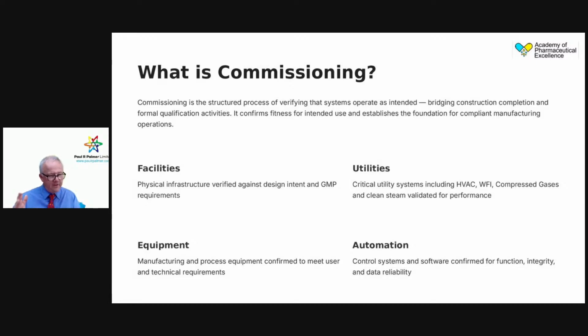Imagine that. You've had your inspection, everything's fine. We've looked at how you're going to do your commissioning, what your plan is, based on your SOPs. But then you go to the site and they won't let you take any pictures, and they won't let you take your digital notebook into the facility because they've got a higher specification than you're used to for particulates. But if you've not got the evidence and you cannot prove that equipment is working according to the specification, because you didn't adequately control the data from your commissioning, how are you going to prove it? How are you going to show that it works? Think about that in your next risk assessment.